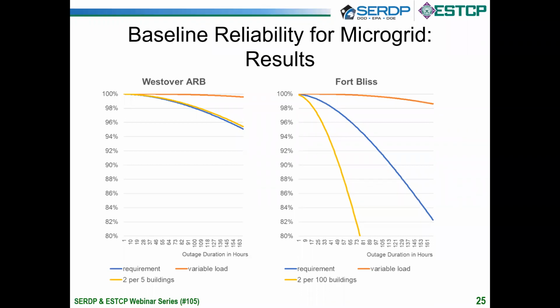one fails. I'd like you to compare that to the probability of meeting 100% of the critical load if you had not a microgrid, but 2 generators tied to each building with a critical load, in this case assumed to be 100 buildings. That is the yellow line. You see that that very rapidly dies off. What that's telling you is that in the absence of a network solution, the likelihood to meet all your critical load is much lower than most people's expectations.